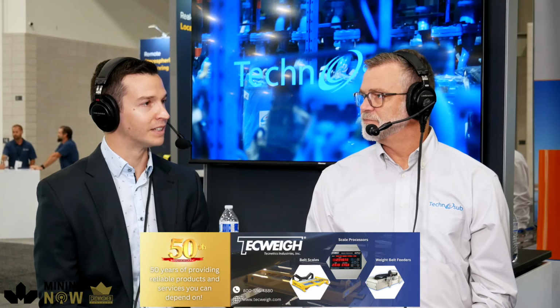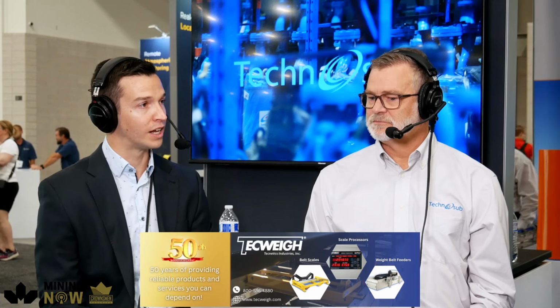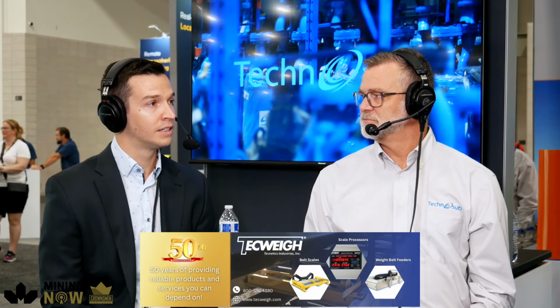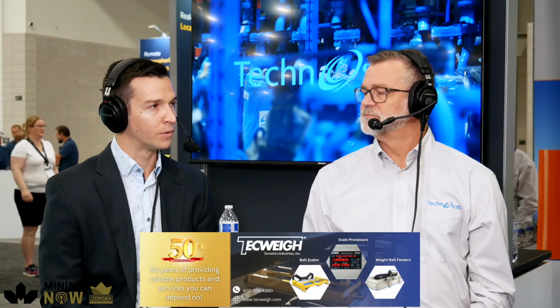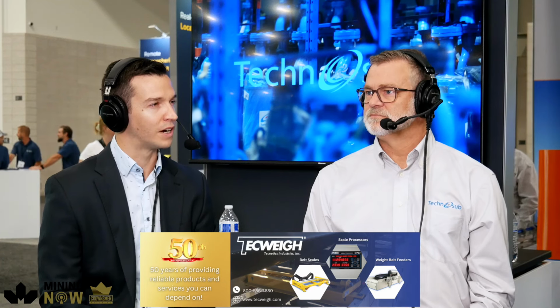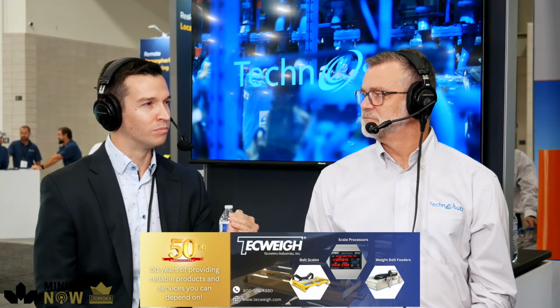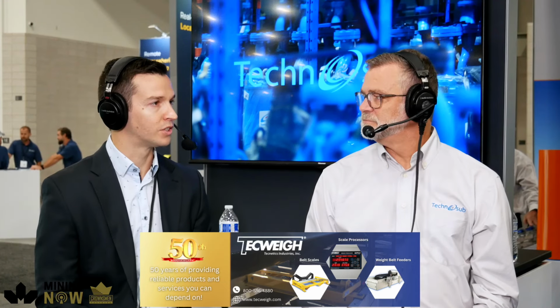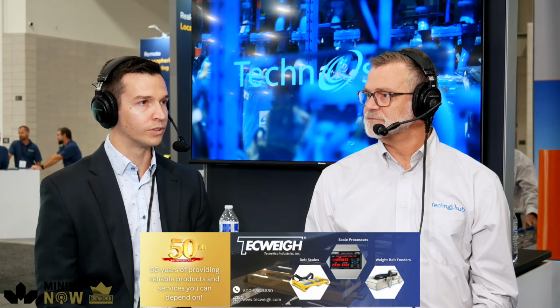So this is where the technology and collaboration we're doing right now is very useful to the water management team, because most of the technologies that exist right now for health or reliability monitoring of assets are mostly just about vibration. You'll have tracking on the vibration level, with low-level alarms, mid-range, high, and trip, so you're going to stop a pump. Some companies, and we've seen them all around here at Mine Expo, have a bit more capability on diagnostics, like high frequency analysis, FFT, vibration spectrum, to identify things like misalignment or soft foot.